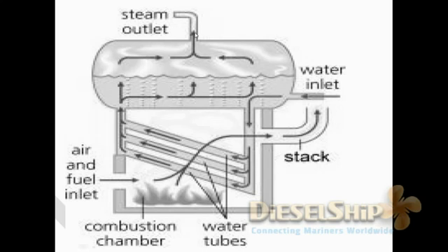Here we have the steam and water drum, where the feed water inlet is here, and here is the downcomer. Please note this point. Here is the downcomer. It's inside the boiler, so it's called an internal downcomer, and these are the generating tubes or the risers, which produce steam and then return it to the steam and water drum. The steam which is formed gets collected at this space, and the steam outlet is over here, and here is the burner. The exhaust gas flows through the stack.